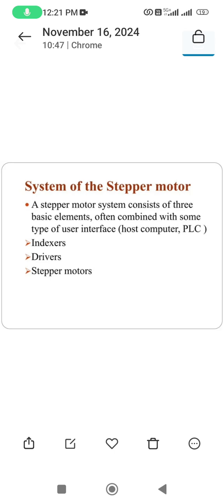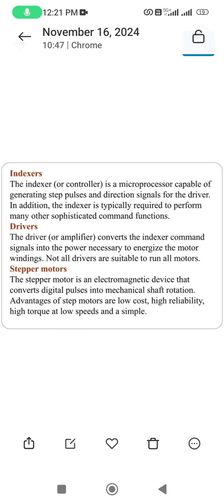A stepper motor system consists of three basic elements: indexer, driver, and stepper motor. The indexer is a controller — a microprocessor capable of generating step pulses and direction signals for the driver, and performs many other sophisticated control functions. The driver, or amplifier, converts the indexer command signal into the power necessary to energize the motor windings. Not all drivers are suitable to run all motors.